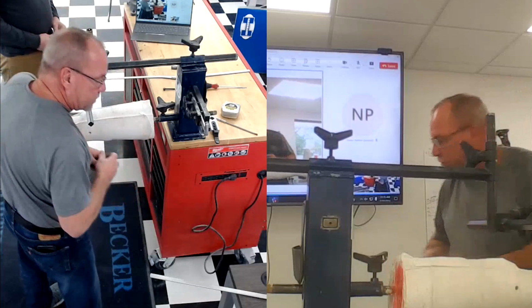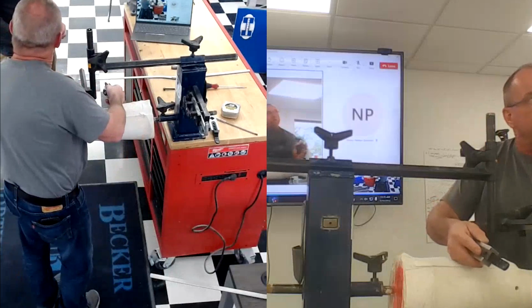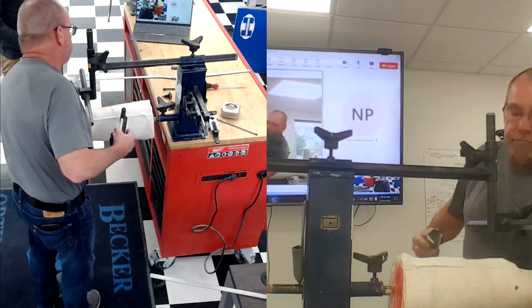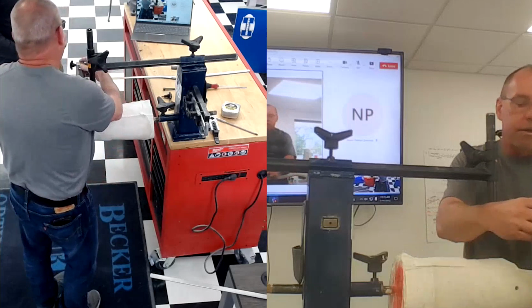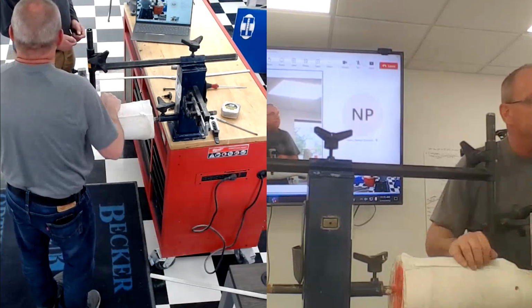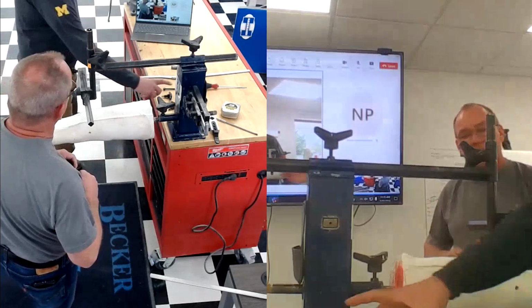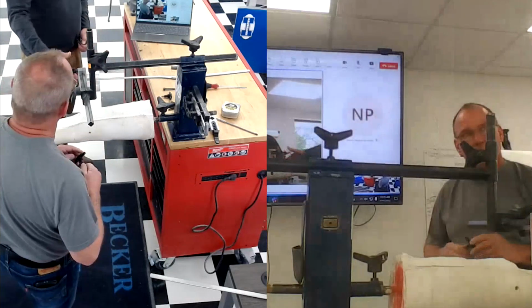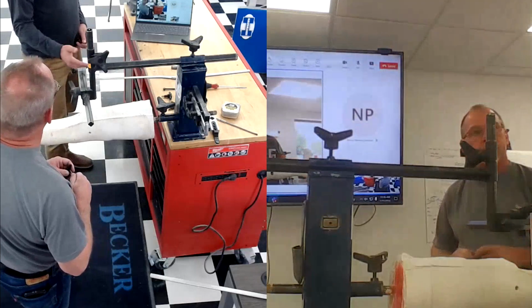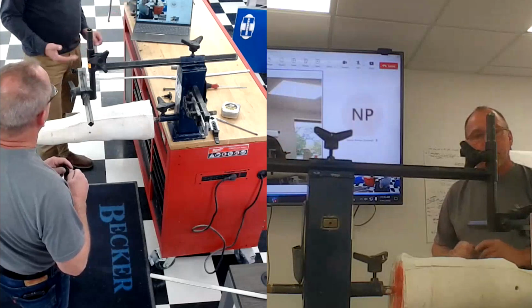And I could put those screws through the handle and into the bushing that exists in the knee joint. A longer bolt or screw that can reach. Yep. So once it's on there, the joint goes behind it. I know we've customized some tools for ourselves too that have a longer length and depth. Sometimes you need to do that for a varus or valgus knee position. Exactly. Or different joints being used in the field that a customer may send to us.